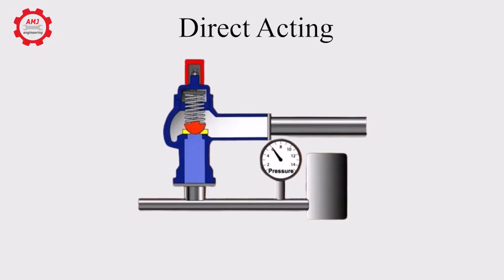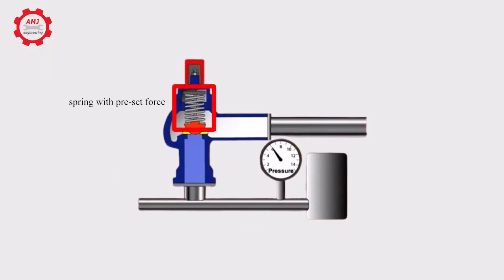Two types of pressure relief valves are there. Direct acting. A direct acting valve may consist of a poppet or ball, held exposed to system pressure on one side and opposed by a spring of preset force on the other.